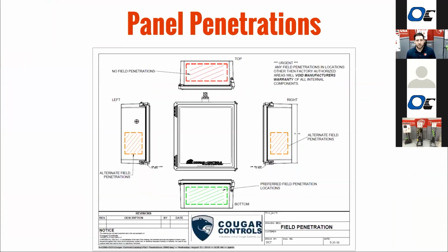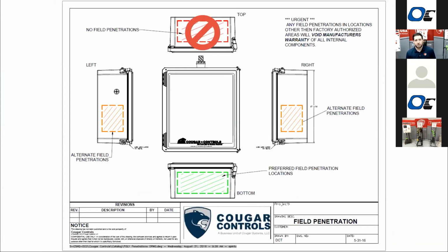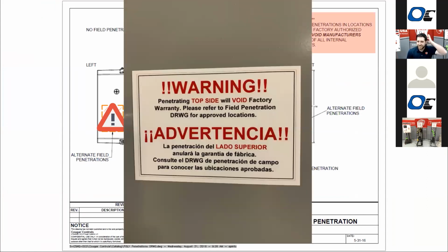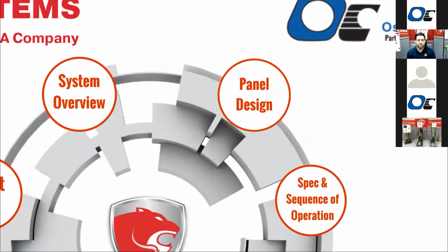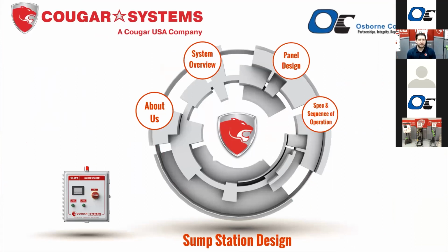And then again, just a little bit on the field penetrations there. Any of our panels, we're always not going to allow penetrations to the roof. Actually, it would void our warranty, and we have a big sticker that we put on top of all of them to discourage against those. We've had issues here with regular conduit being used in the tops of these panels, and allowing water to drip inside and ruin the internals of a control panel.